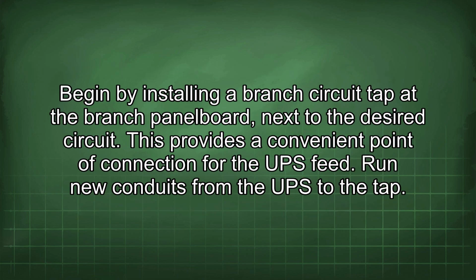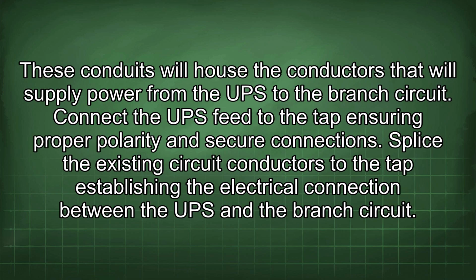Begin by installing a branch circuit tap at the branch panel board next to the desired circuit. This provides a convenient point of connection for the UPS feed. Run new conduits from the UPS to the tap. These conduits will house the conductors that will supply power from the UPS to the branch circuit. Connect the UPS feed to the tap, ensuring proper polarity and secure connections. Splice the existing circuit conductors to the tap, establishing the electrical connection between the UPS and the branch circuit.